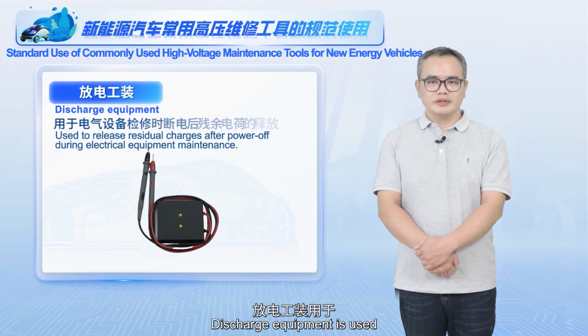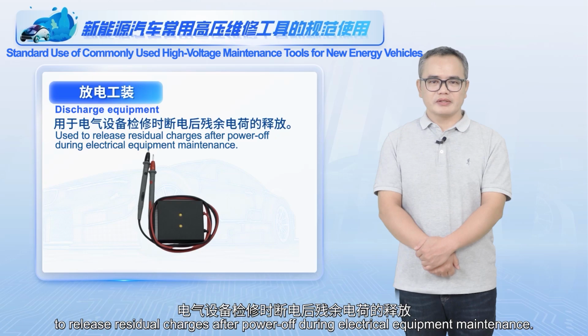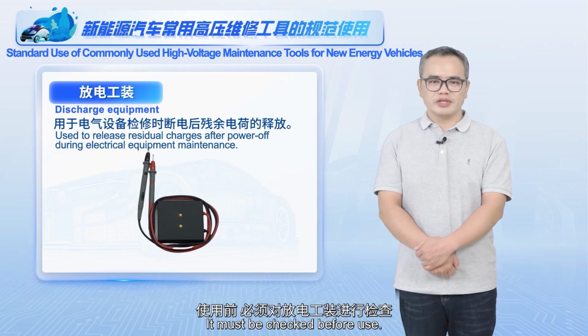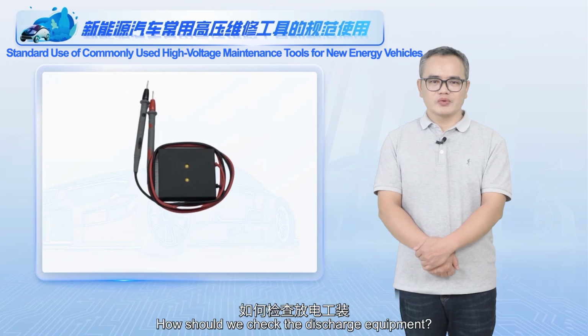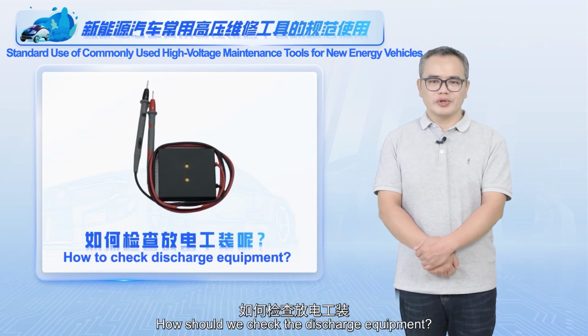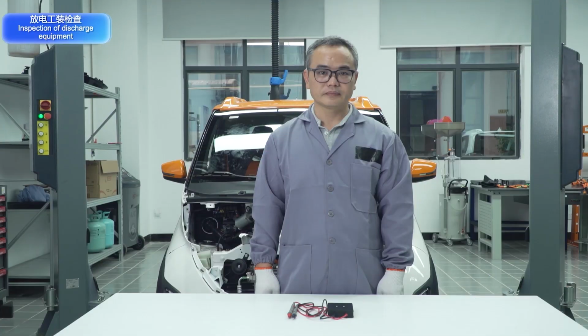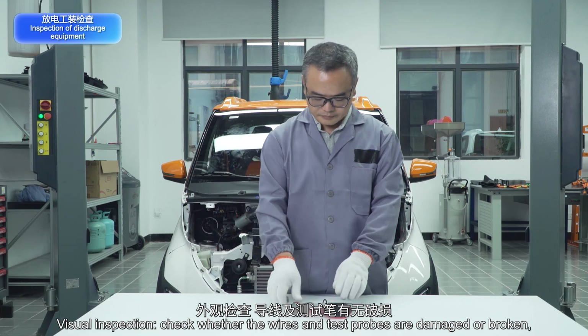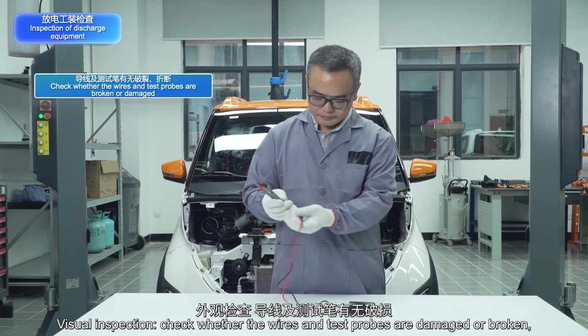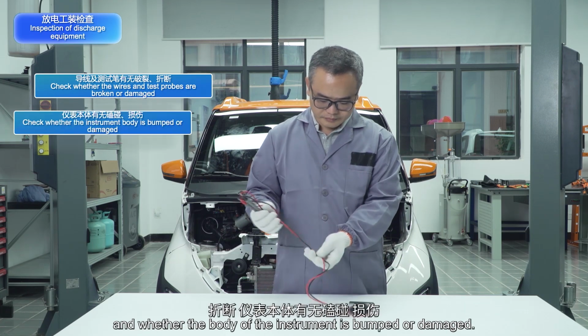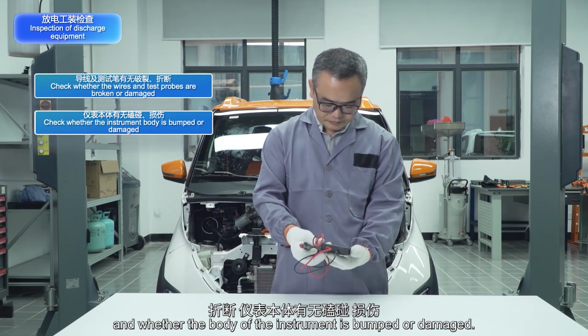Discharge equipment is used to release residual charges after power off during electrical equipment maintenance. It must be checked before use. How should we check the discharge equipment? Visual inspection. Check whether the wires and test probes are damaged or broken, and whether the body of the instrument is bumped or damaged.